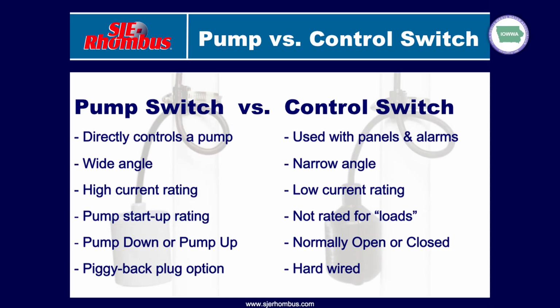Difference between a pump switch and a control switch, there are some inherent differences. And when I say a pump switch, I'm talking about a switch we're going to run full load, full current through the switch to operate a pump. With a control switch, typically that's going to be used in conjunction with a control panel or a high-level alarm where you're going to have a relay. So all we're going to do with a control switch, when it goes up, we'll complete a circuit, energize a relay, and activate an alarm or a motor contactor on the panel.